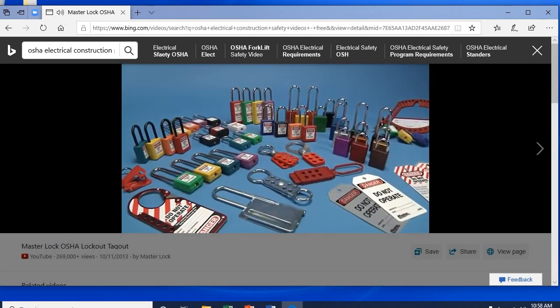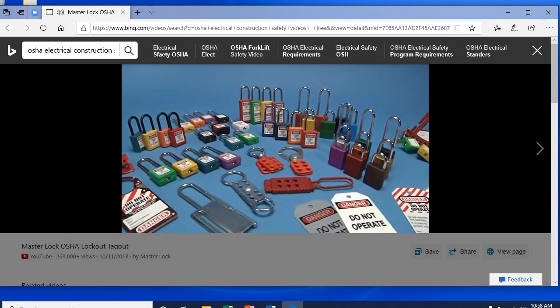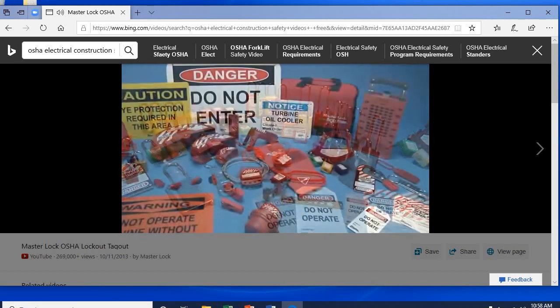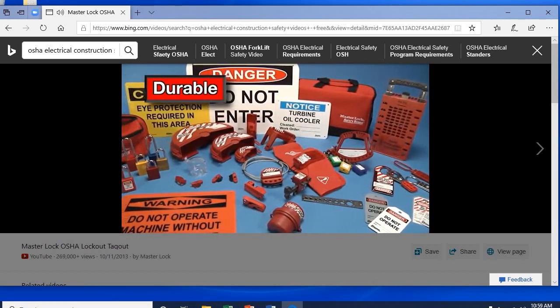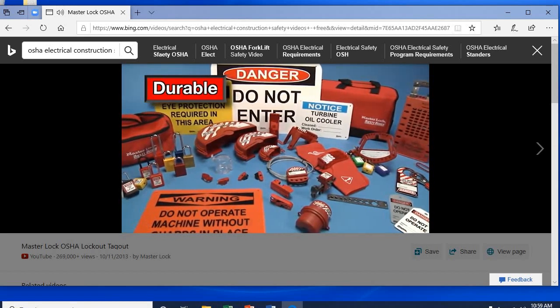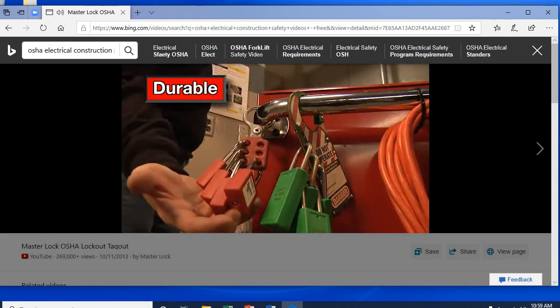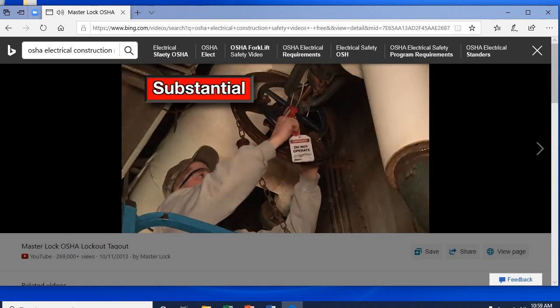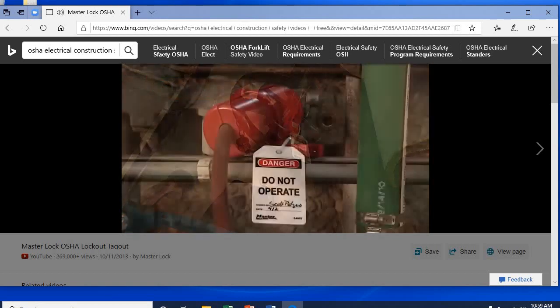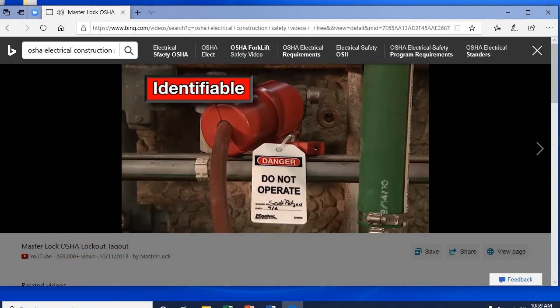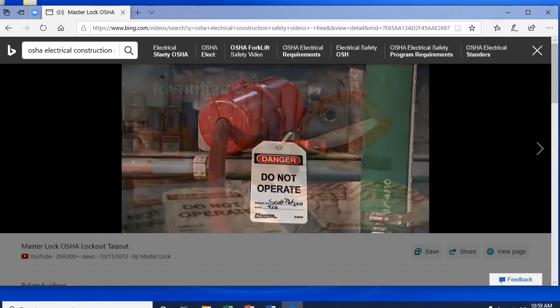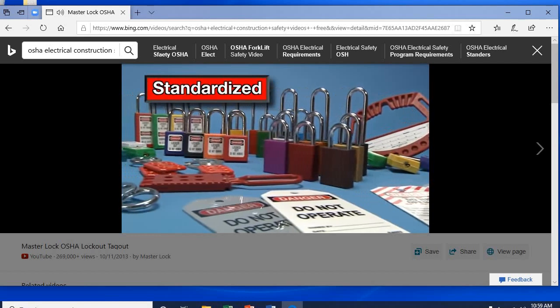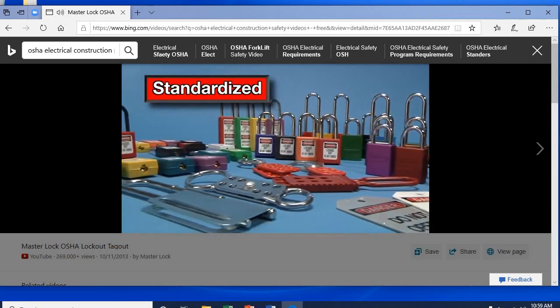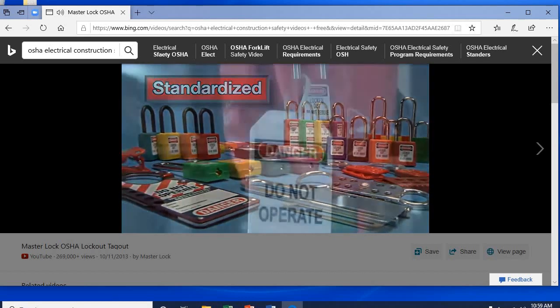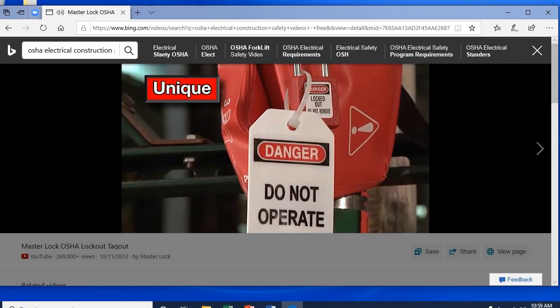OSHA has established the following general guidelines for lockout-tagout devices. Lockout/tagout devices must be manufactured from durable materials to withstand the industrial environment of their use. They must be substantial enough to prevent removal without the use of excessive force. They must clearly identify the employee who installed the device. They must be standardized within the facility by color, shape, and/or size. They must be singularly identified.